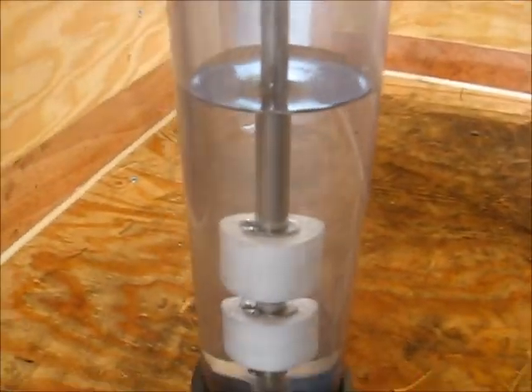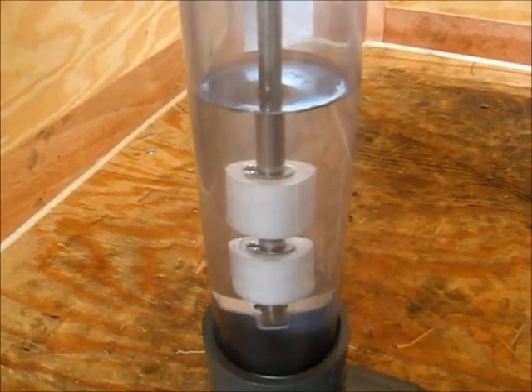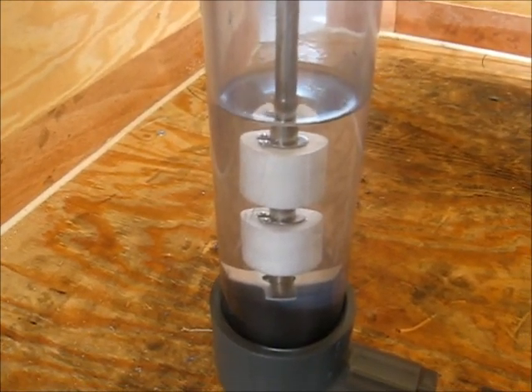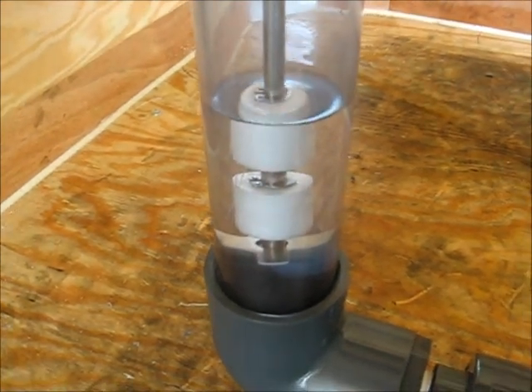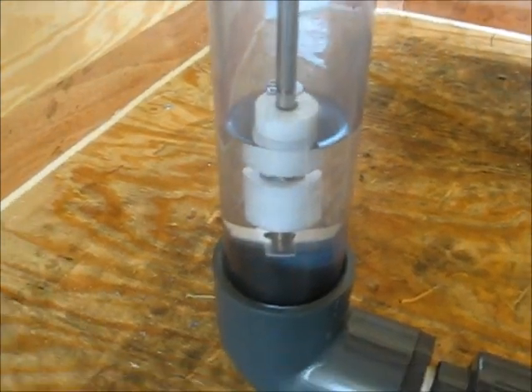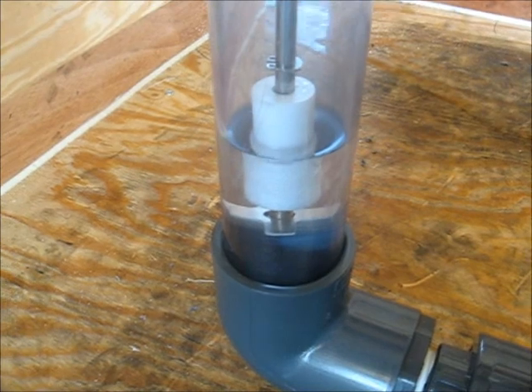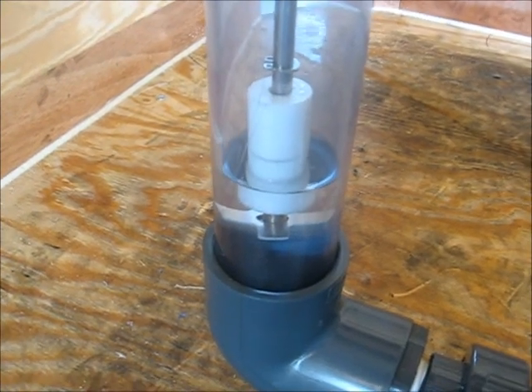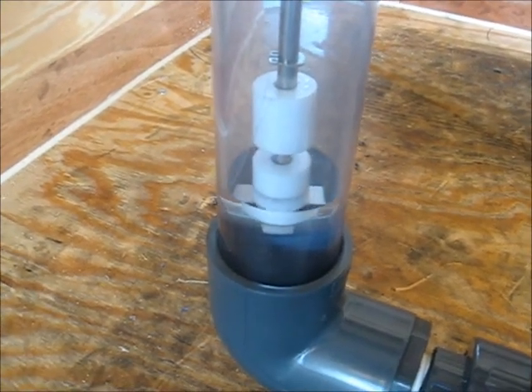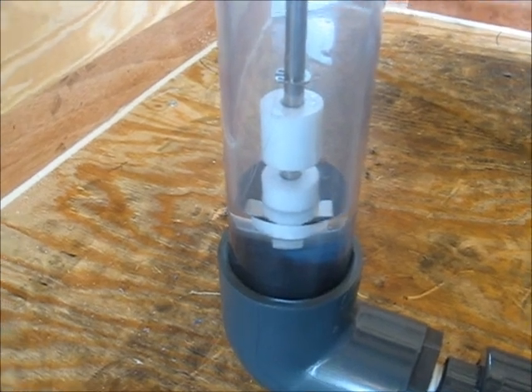Hear it pumping. You see the water level going down rapidly. What we want to see is that the pump stops when we get below this low float. Yep, and there it is. It stopped when it was supposed to.